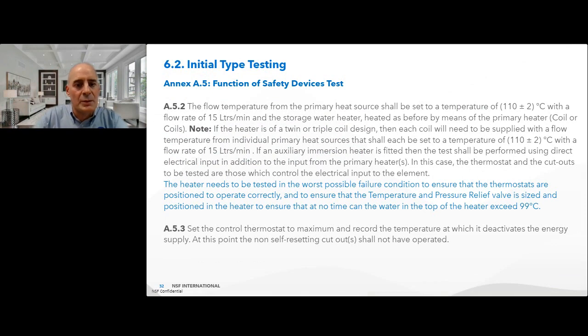The flow temperature from the primary heat source should be set to a temperature of 110 plus or minus 2 degrees with a flow rate of 15 litres a minute, and the storage water heater heated as before by means of the primary heater or the coil or coils. Note that if the heater is of a twin or triple coil design, then each coil will need to be supplied with a flow temperature from individual primary heat sources that should each be set at a temperature of 110 plus or minus 2, also with a flow rate of 15 litres a minute.